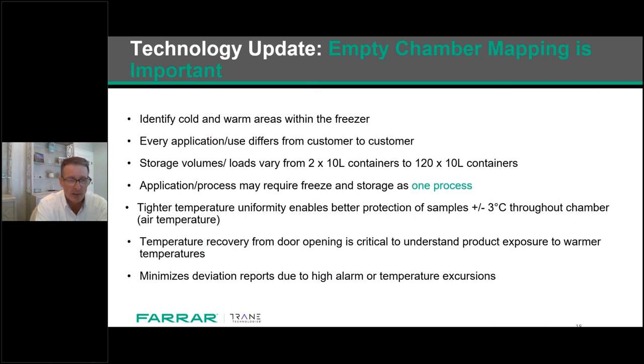So I also want to point out the temperature mapping is one of the most important processes to ensure the proper uniformity within the chamber. I know most of you are aware, you perform IQOQ, and part of the IQOQ is to do a temperature mapping. But the one question, why temperature map an empty chamber, meaning only shelves with no racks? Well, the mapping of an empty chamber provides the worst case scenario of air temperature and uniformity within the chamber.